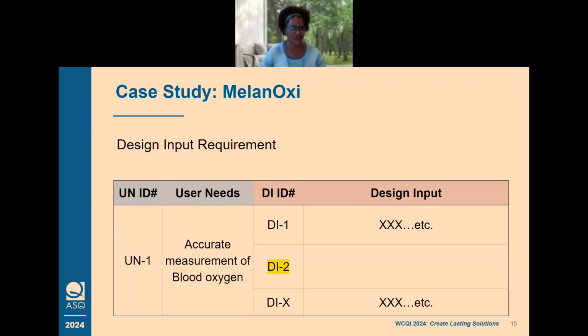So in this traceability matrix, we have identified user need. So we've got UN1, all of the user needs, which are high level requirements. They should all be identified and indexed so they could be traced all the way from the design input all the way through to verification and validation. So we give an example for MelanOxi, which would be user need number one, provide an accurate measurement of blood oxygen. So as you guys who are engineers know, user needs can have multiple design inputs.